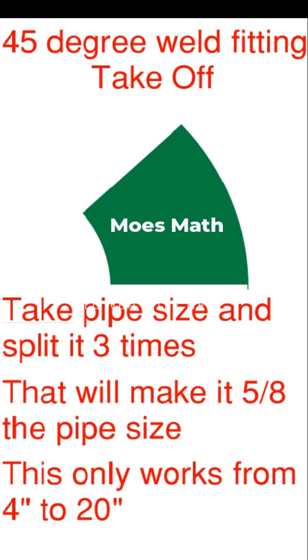You take the pipe size and you split it three times. That will make it 5 eighths the pipe size. This only works from 4 inch to 20 inch.